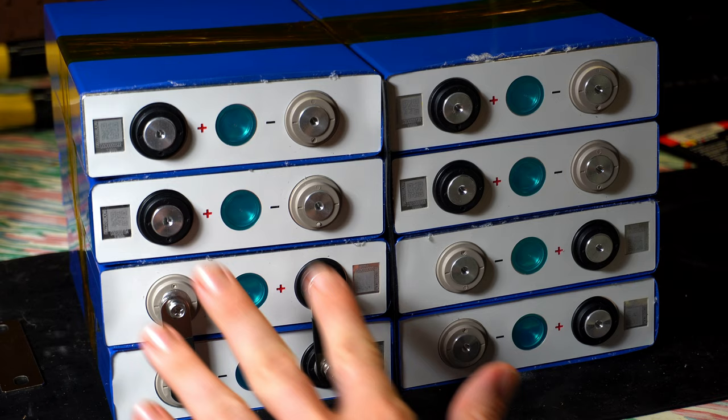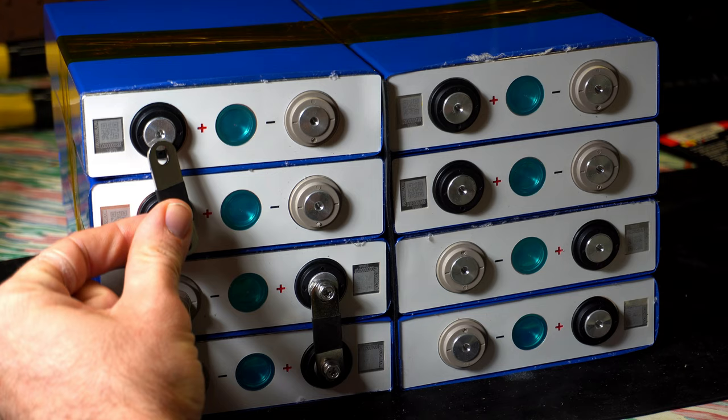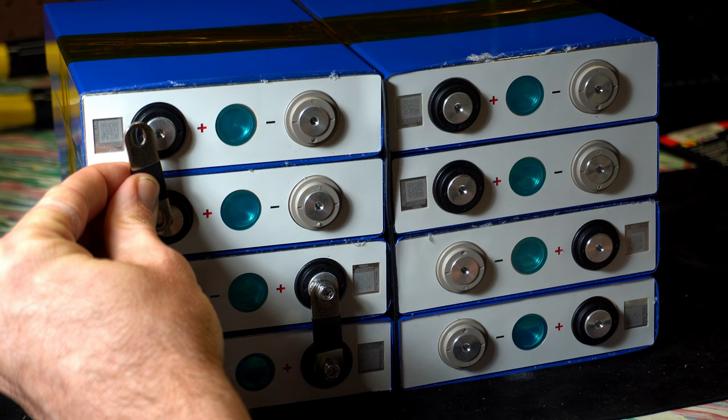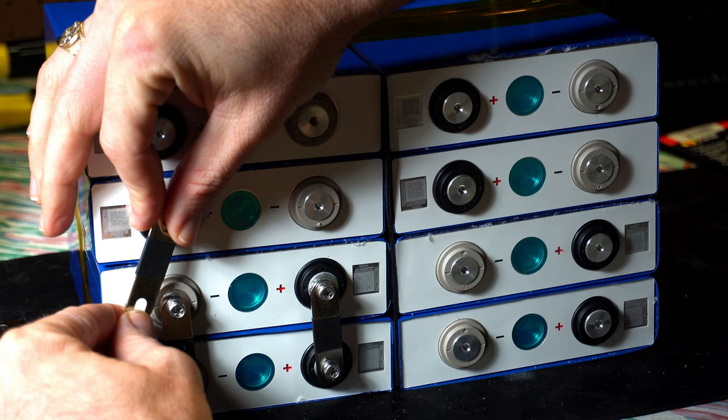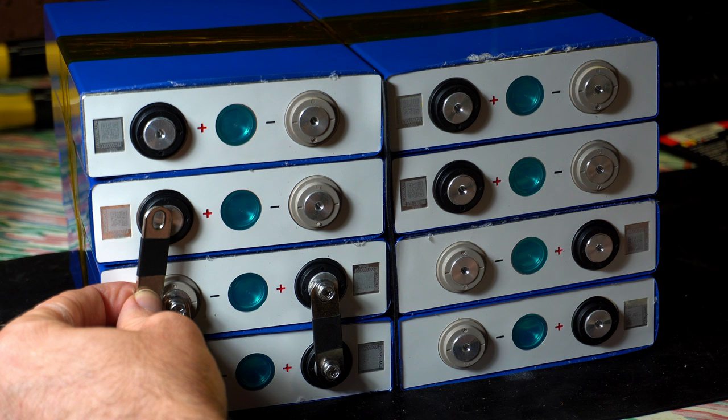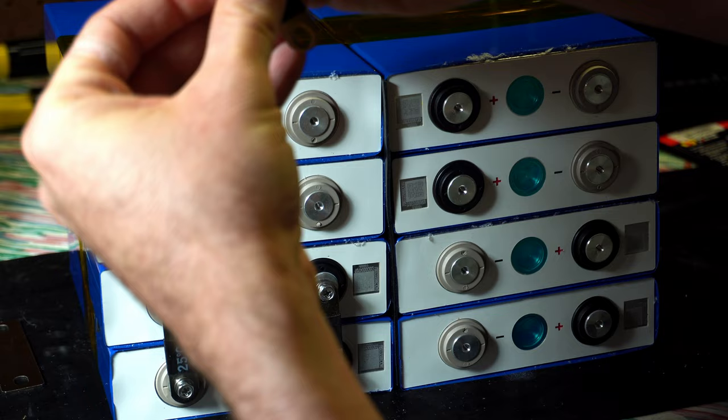Now that we have this first set set up in parallel, we're going to do the next one. A really important thing: when you're doing this, you always want to do the highest one first. Always consider gravity in your situation. If we attach the first screw on the bottom and then we let go to put the top one on, when we let go, what if this guy spins and comes down and makes contact down here? We just made a short circuit and stuff can explode. Always start on the top and let gravity hold your pieces until you're ready to finally put them in.